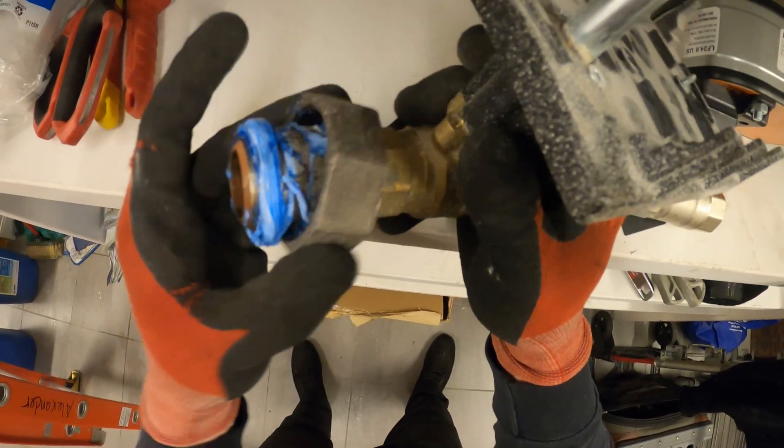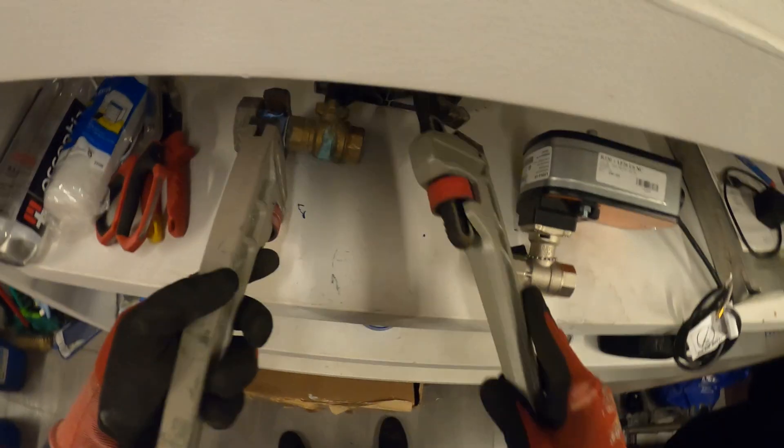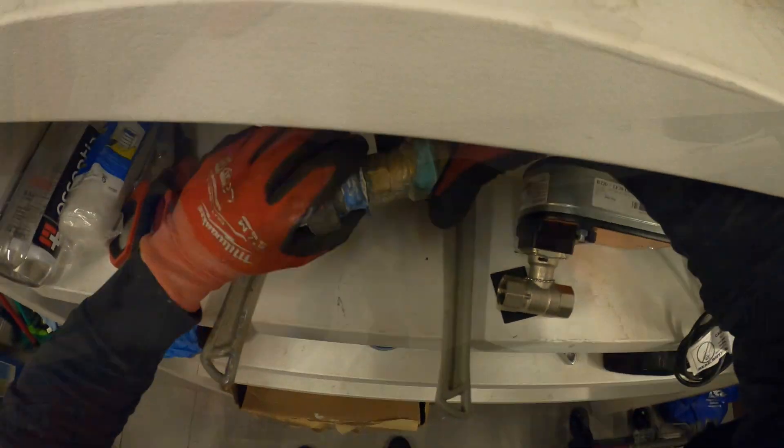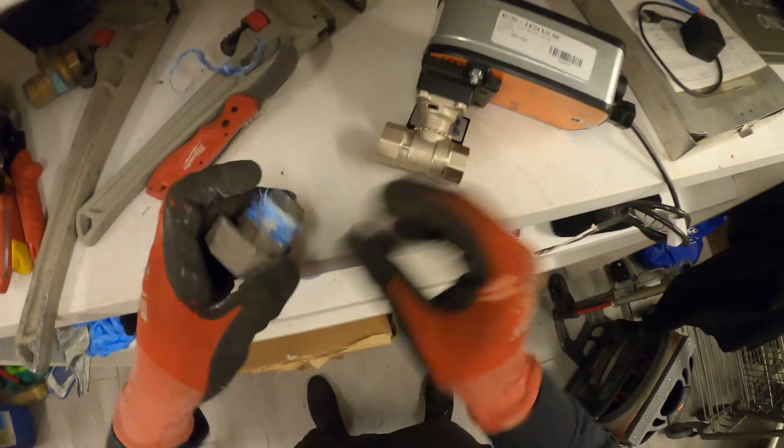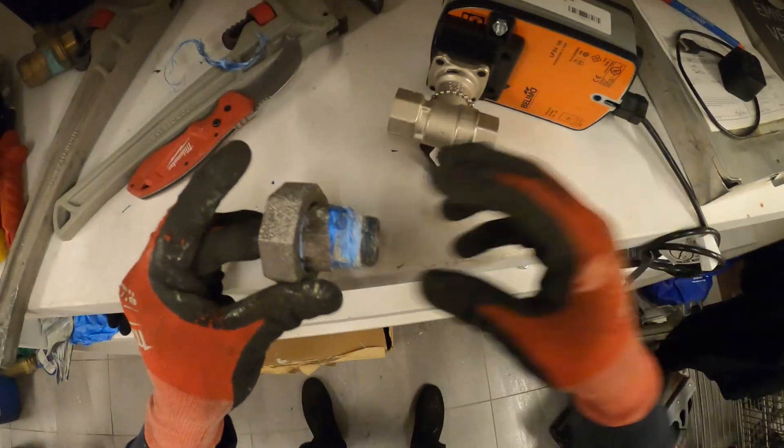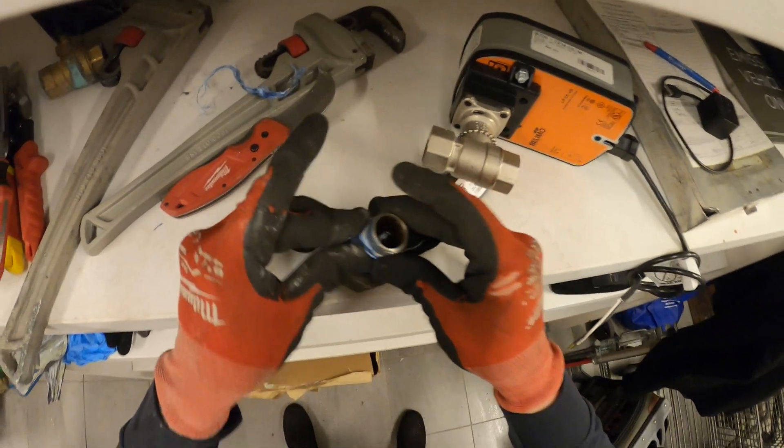It looks like previously they had an issue with this union leaking because there's Teflon tape on the union and you really don't need that. So just something to be cautious about. We're going to reduce some of this Teflon. And we're basically just going to attach this now into this piece and just redo everything the opposite way.